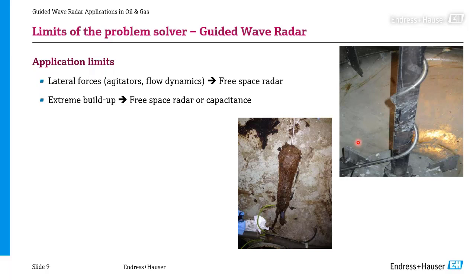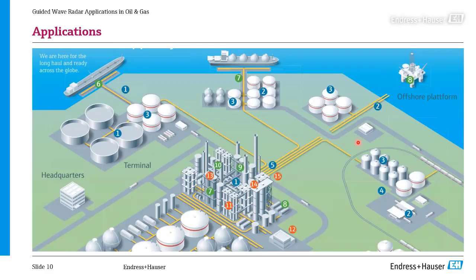The other point is extreme buildup. Whenever you have too much buildup, you wouldn't want to put such a guided wave radar into the vessel, because this will just make your measurement wrong. There we would also say go for free space radar or also capacitance probes where we have our active build-up compensation integrated. So, and with this, I hand over to the applications.